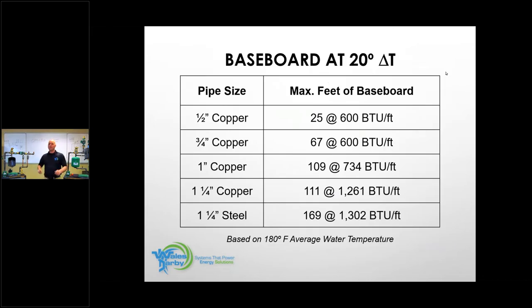So when you get into some of these jobs, and a lot of these are not handouts, you want to take a phone snapshot, have at it. If I have 3/4 pipe going to a heat circuit, the maximum amount of baseboard I can have on that heat circuit is 67 feet. And that's at 600 BTU per foot. And if I do that math, that will basically tell me I'm at about 40,000 BTU. So that's about the average number that we want to move through 3/4 inch pipe, would be 40,000 BTU.